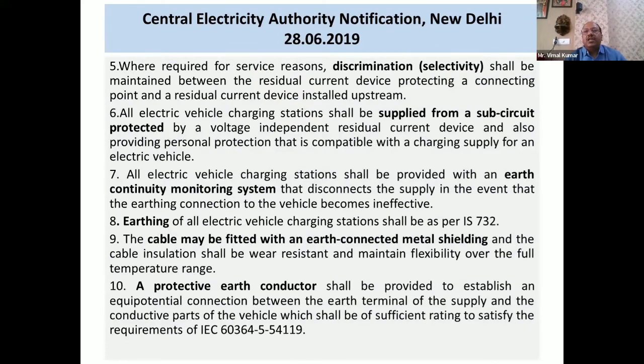It also talks about discrimination in the power distribution for the residual current device, so there is an intelligent decision as to which part has to trip while tripping. A separate circuit has to be given for the EV charging infrastructure, rather for each piece of equipment. It will be still better if the combined system as a whole is provided with a separate substation, particularly for the large PCS. And of course, it talks about the earth conductor also, earthing also.